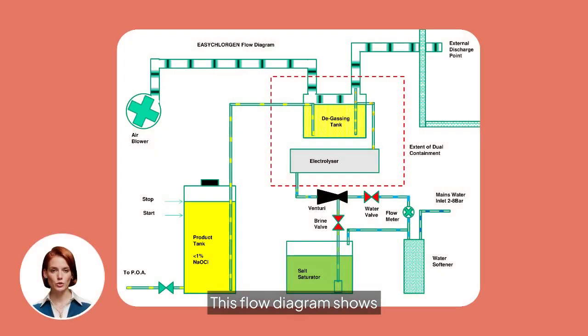This flow diagram shows the standard Easychlorgen process. Softened water and salt form brine, which passes through a venturi into the electrolyzer. The product then enters a degassing tank before reaching the hypochlorite storage tank. An air blower and external discharge point safely remove hydrogen.